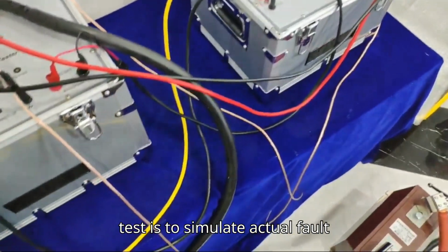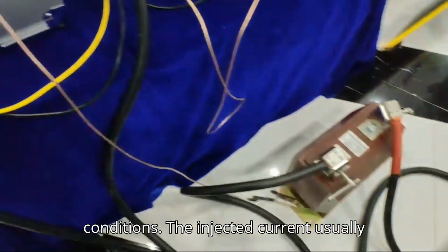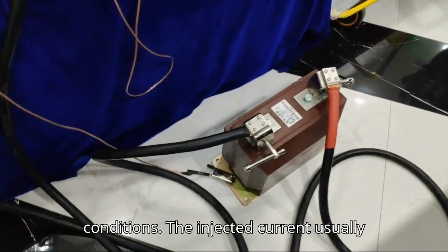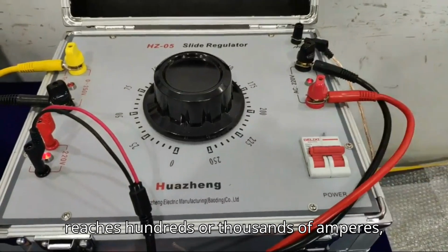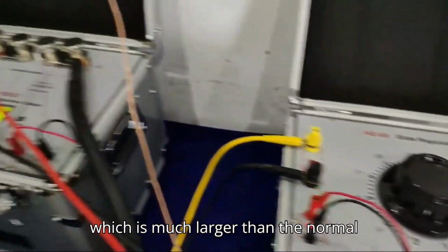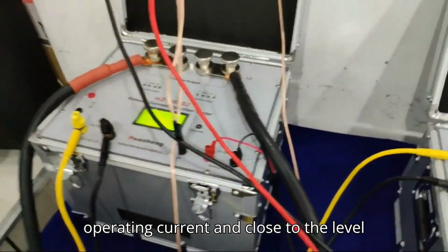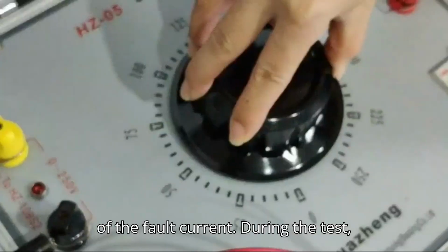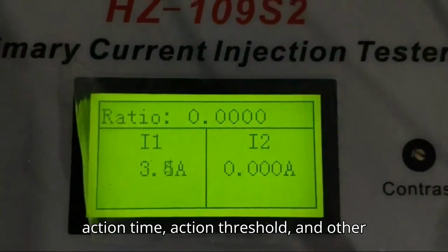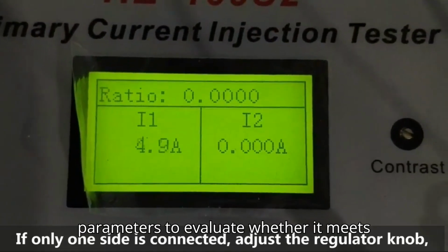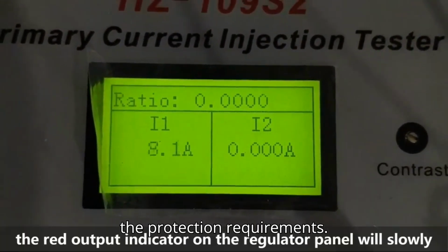The core of the test is to simulate actual fault conditions. The injected current usually reaches hundreds or thousands of amperes, which is much larger than the normal operating current and close to the level of the fault current. During the test, the instrument monitors the equipment's action time, action threshold, and other parameters to evaluate whether it meets the protection requirements.